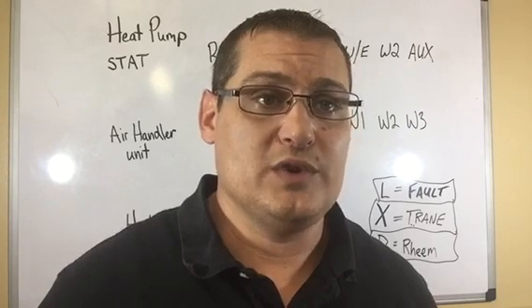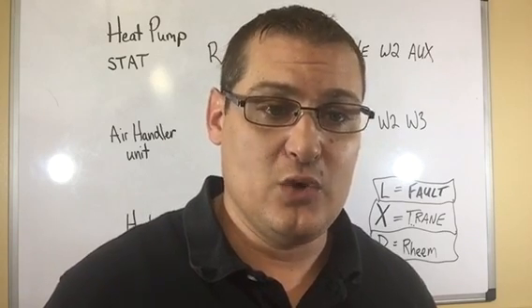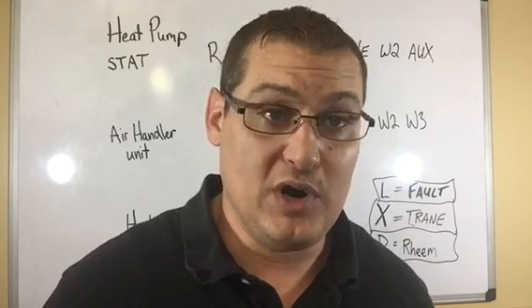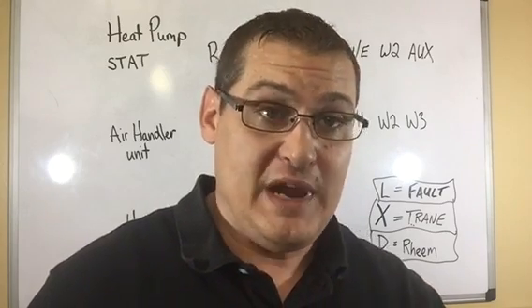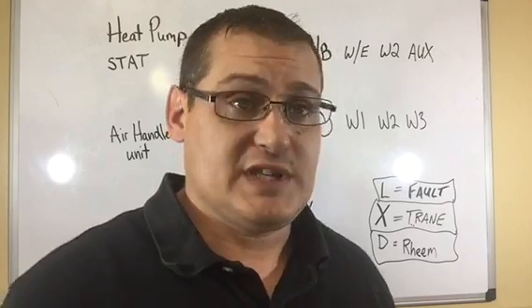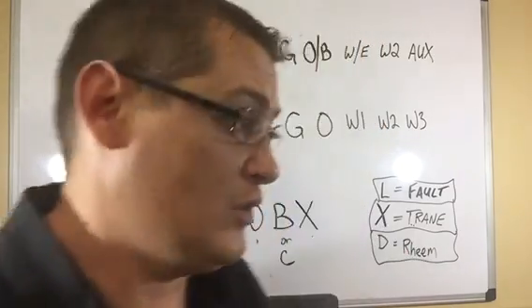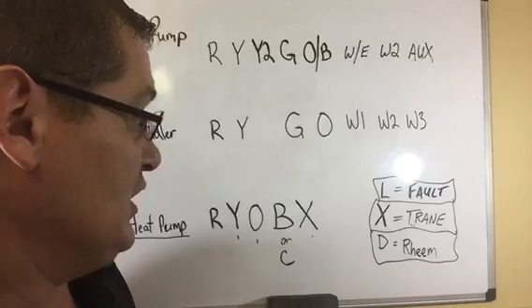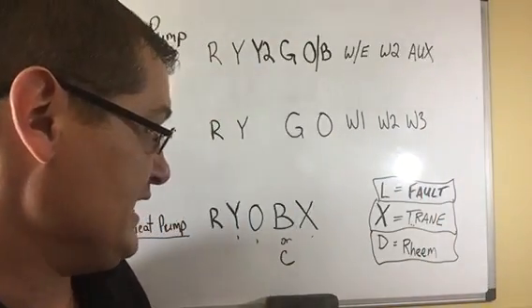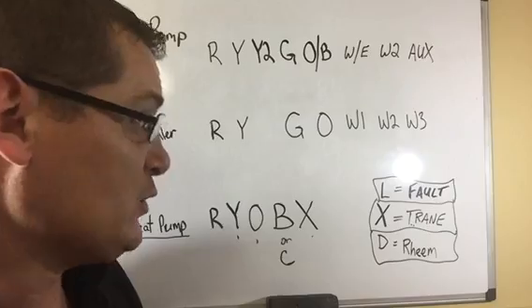During cooling mode, when you flip the thermostat to cool, the outdoor heat pump is just an air conditioner. It acts exactly like every other air conditioner. The difference is the reversing valve and the defrost board. Like we talked about, the O and B terminal, depending on what energizes it for that particular brand and make, depends on what's going to happen with a call for heat or call for cool.